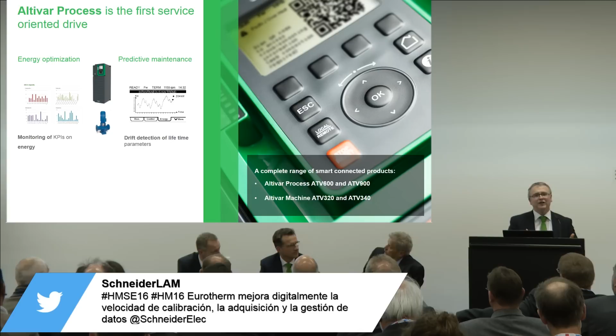They can also act as a sensor for the actuator driven or controlled by the motor. Taking the example of a pump, the drive, acting as a sensor, can detect drift and tell the plant there's something wrong—the pump isn't operating at the right point, or there's going to be a mechanical failure in the coming days or weeks, depending on the type of pump.